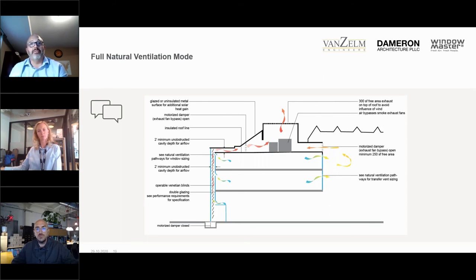As space temperature started to increase, we turned the fans on, designed to operate at low speed so they were quiet—not ramping up to 100%. They were all on VFDs. So when outdoor conditions started to get elevated, we could still meet comfort levels with an advanced increase in airflow and air movement. We'd turn on those fans and utilize the same openings and airflow movement, but in mixed mode. That's covered in the second slide.